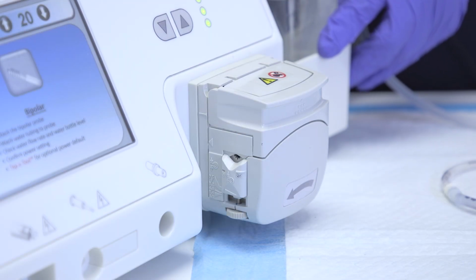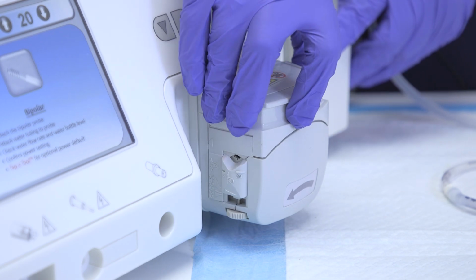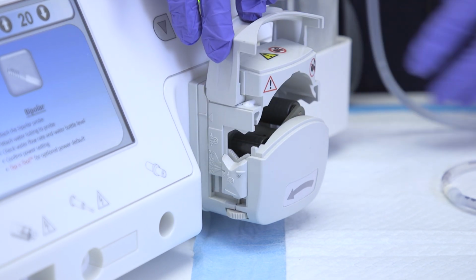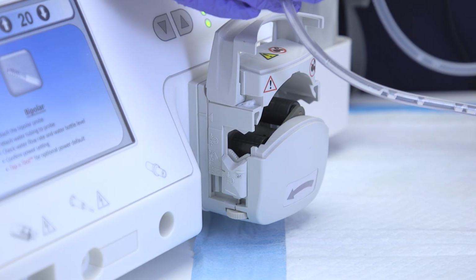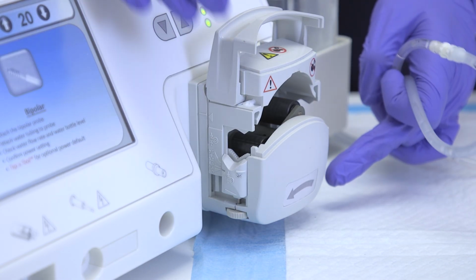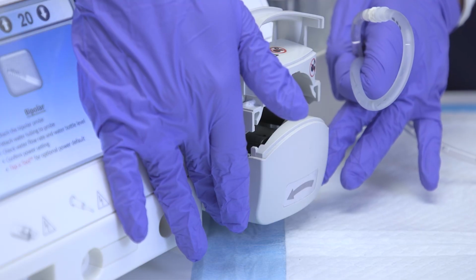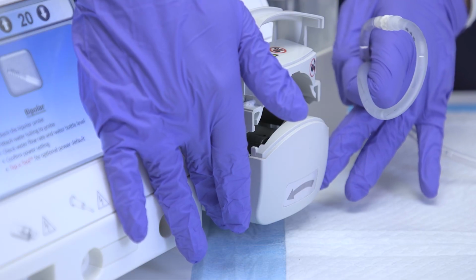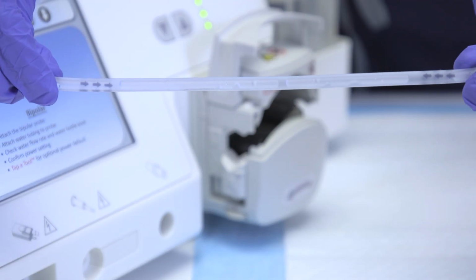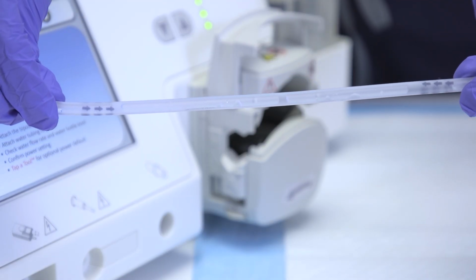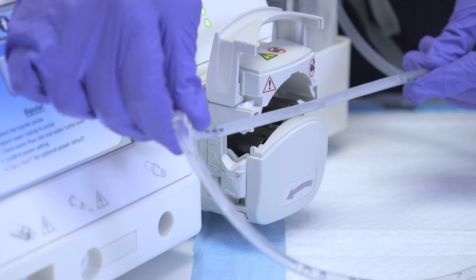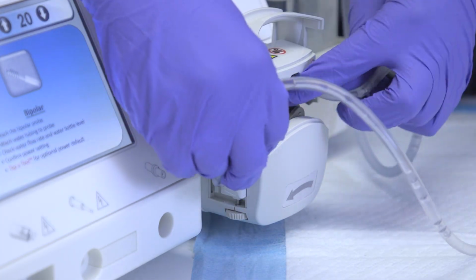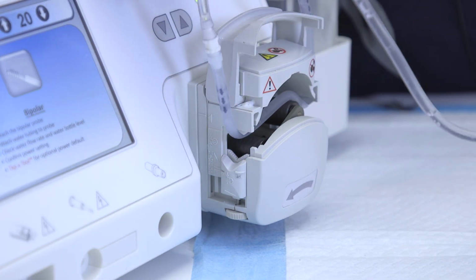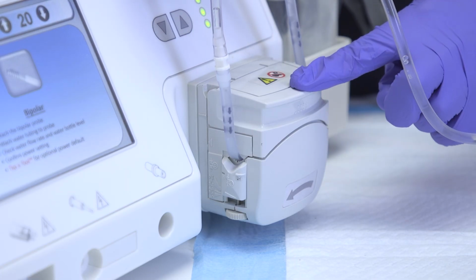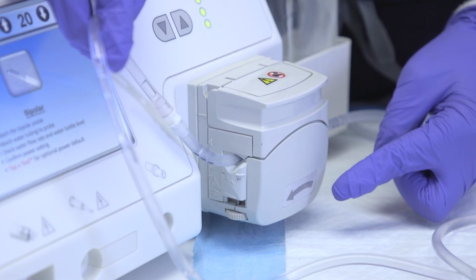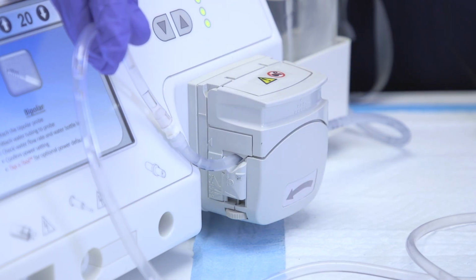After the lavage is loaded into the sterile water bottle, you'll want to open the pump head fully. We recommend using STERIS 1561 tubing. That tubing would align with the 3.2 dials on the side of the pump head. You can always adjust the pump head for different tubing. Locate the arrows on the flexible roller section of the tubing. Load the tubing into the pump head. Pull up, shut the pump head, and the arrow indicates the flow of the irrigation.